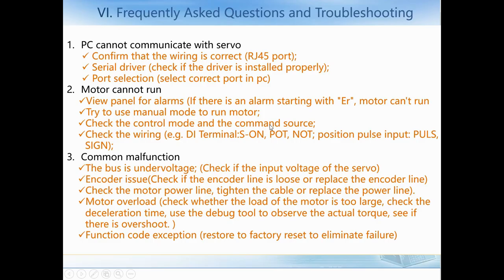Now we'll talk about FAQ and troubleshooting. The first question: if the PC cannot communicate with the servo, confirm which COM port is selected, check the driver installation — if the driver is not installed properly the communication will fail — and check the port settings. If the motor cannot run, first view the panel and check if it displays RDY or RUN on the LED. Second, try using manual mode to run the motor. Third, check the control mode and command source. Last, check the wiring, such as S-ON, POT, NOT.